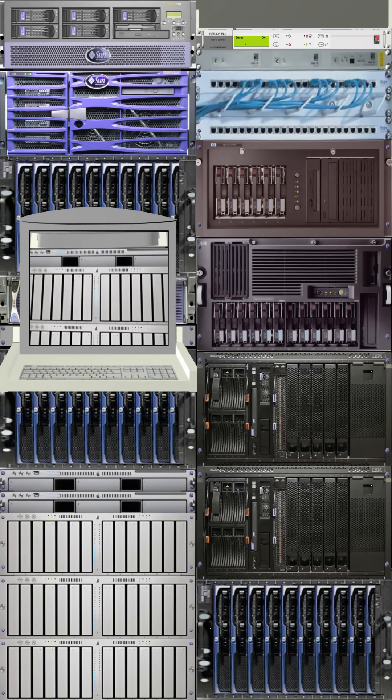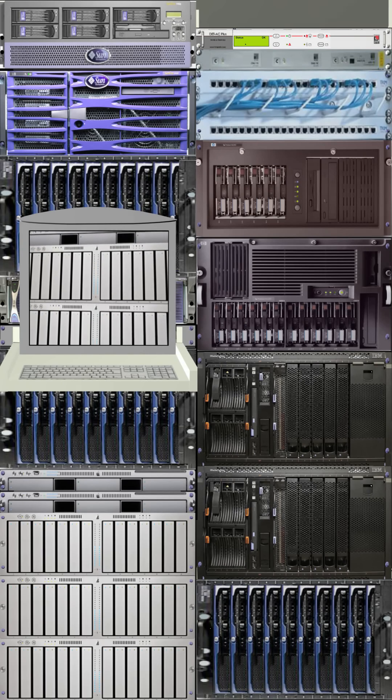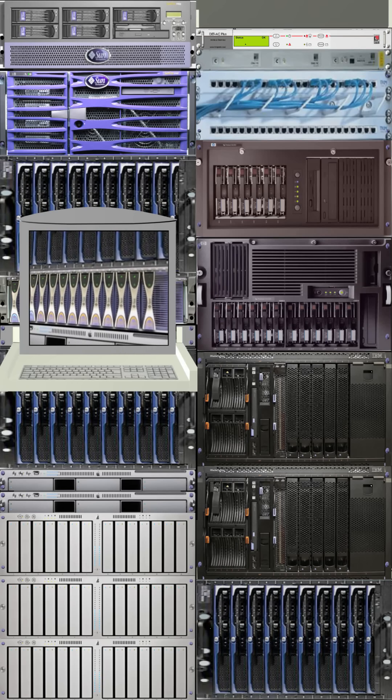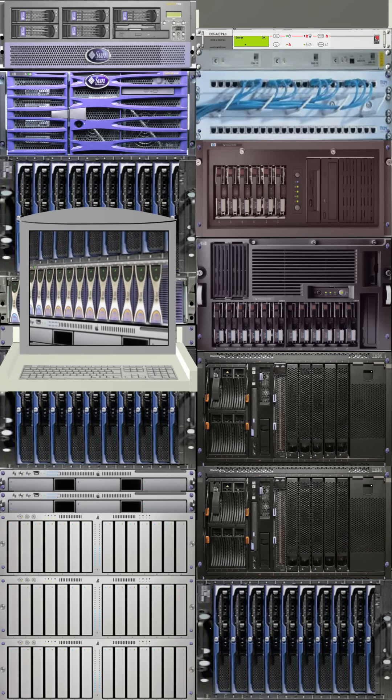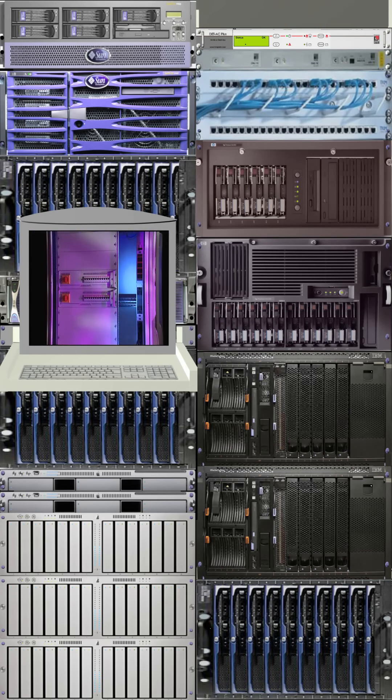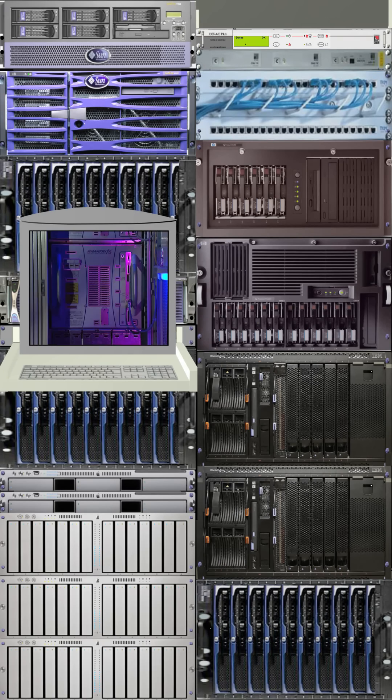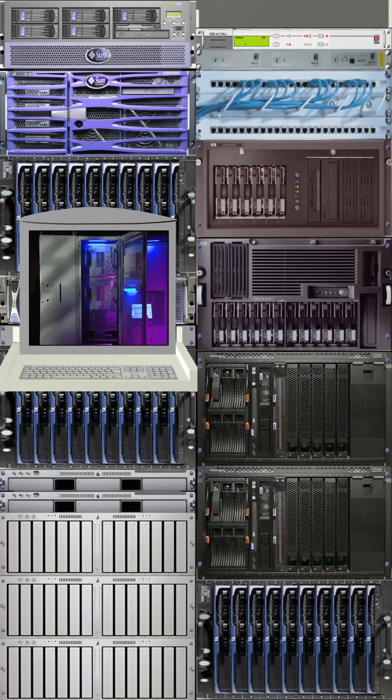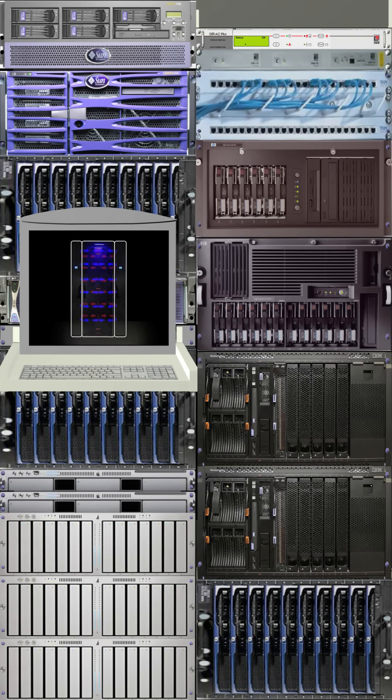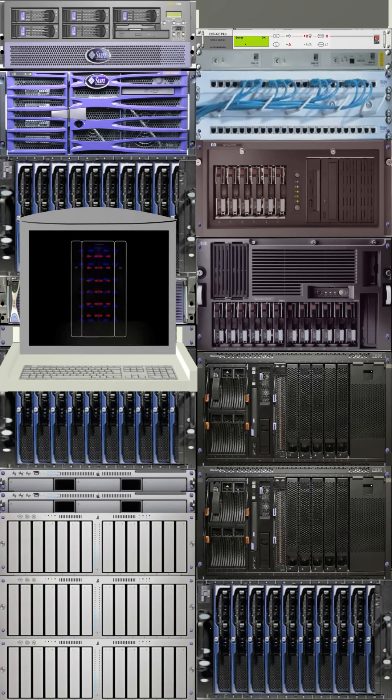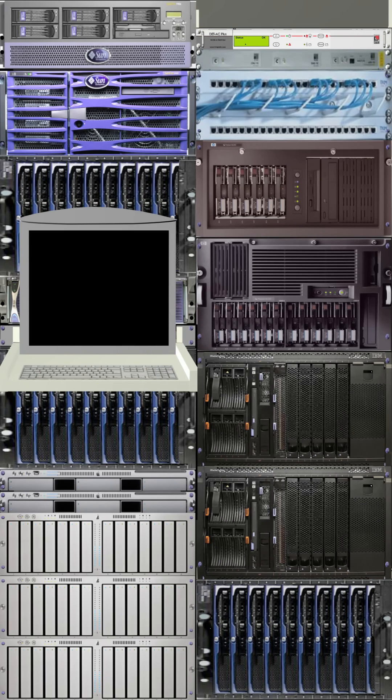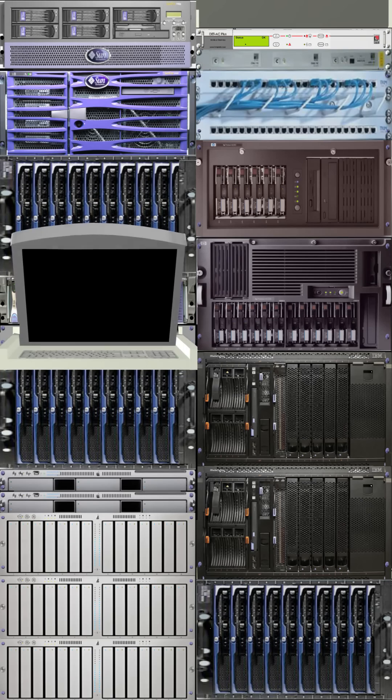Typical backup best practice includes mirrored servers and RAID arrays that provide the IT hardware with redundancy. On the power side, each server now typically has dual redundant power feeds and in turn, each feed is supported by a UPS that may have its own redundancy UPS or backup generator supply. Even the thermal aspect of data center design is covered by N plus 1 redundancy. All of these really only protect uptime and data though. What happens if you have a fire?